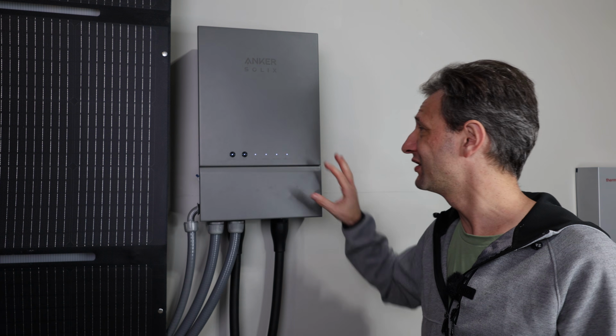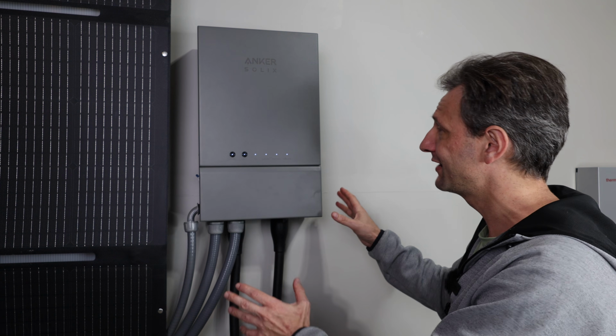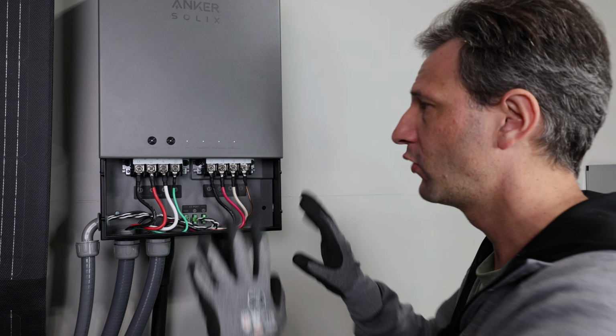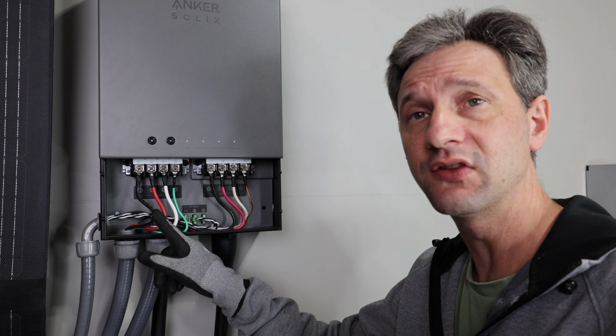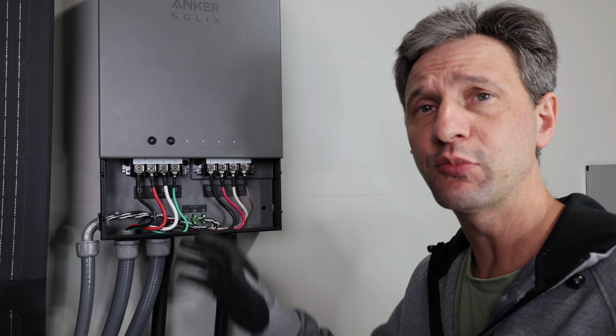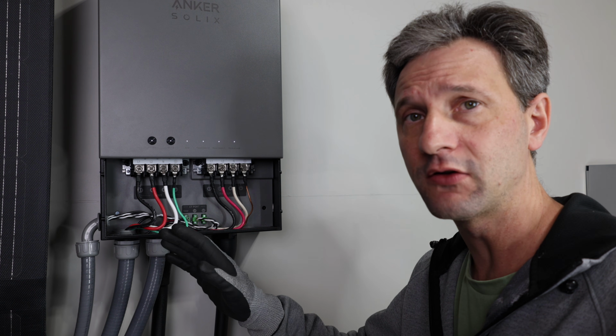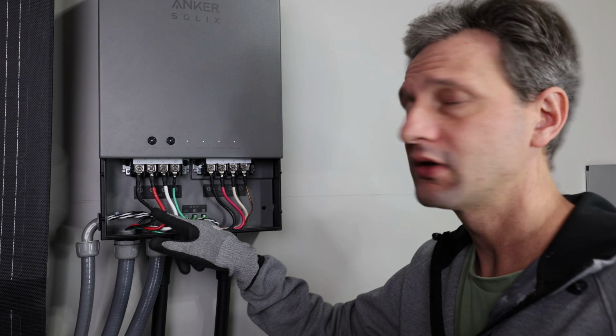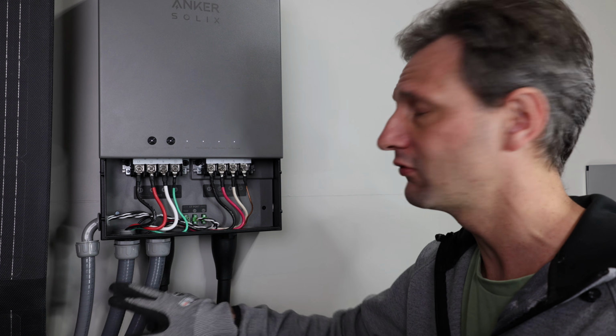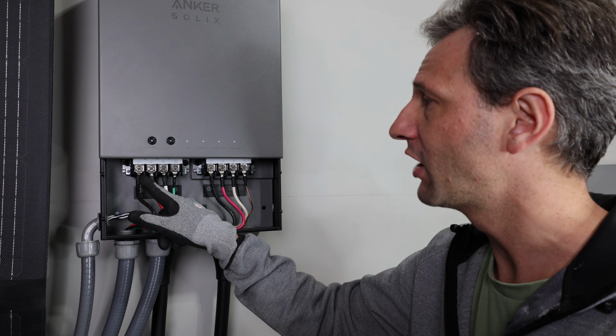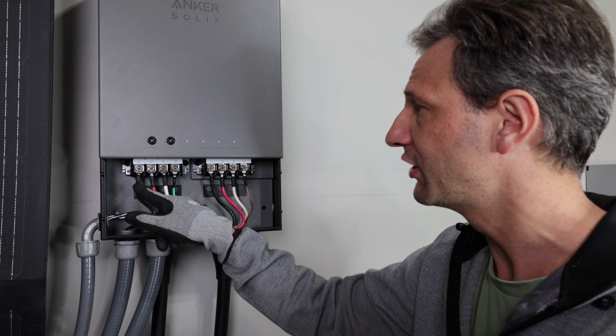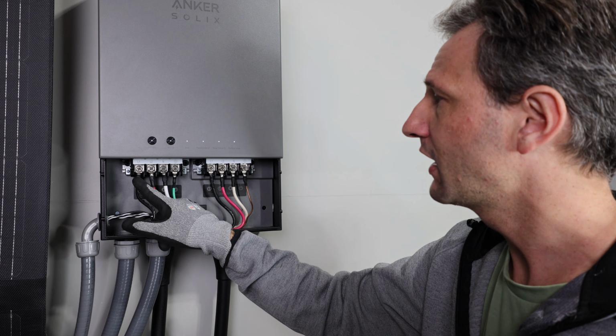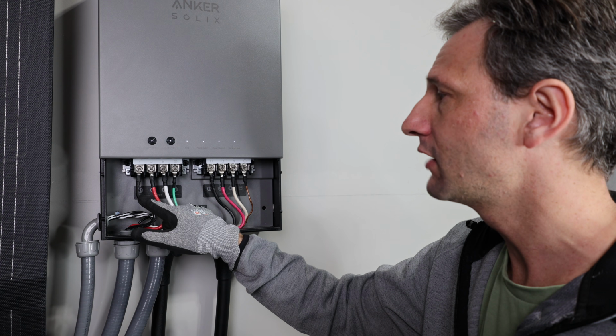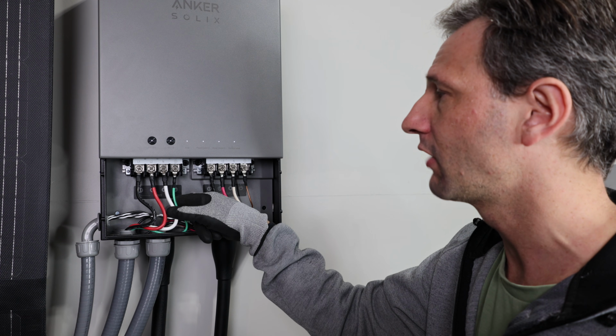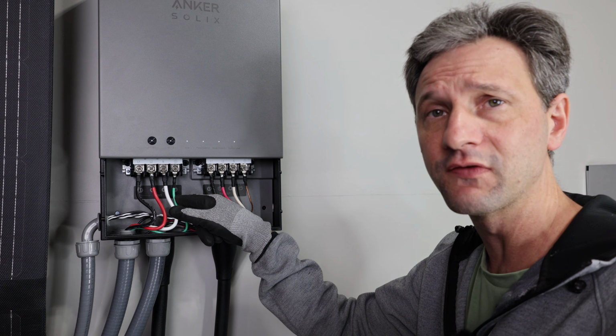The installation for this unit is really pretty simple and nice and clean. We have two main connections - the first is the grid input. I just put a 50 amp breaker in my main panel and connected it with 6 gauge THHN through a flexible conduit. I put some eyelets crimped on the end of the wire, a little bit of heat shrink to keep things nice and neat, then torque these down. I have line 1, line 2, neutral, and ground. I can use a 10 gauge ground here since it's a 50 amp breaker.